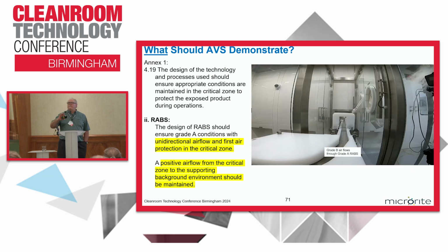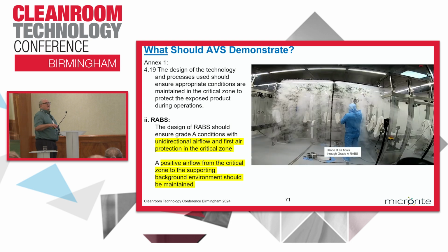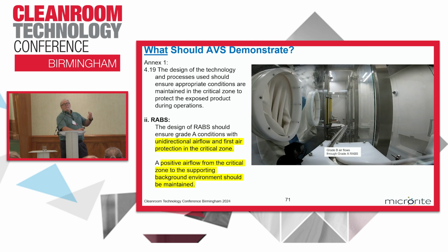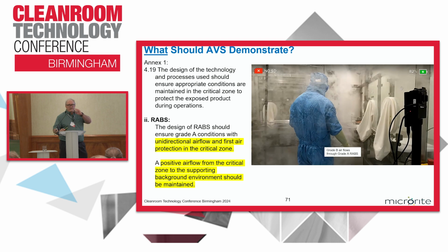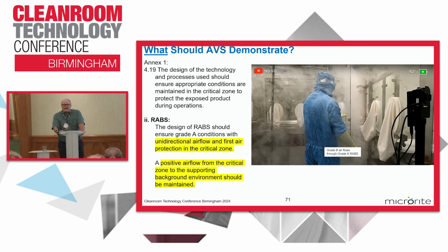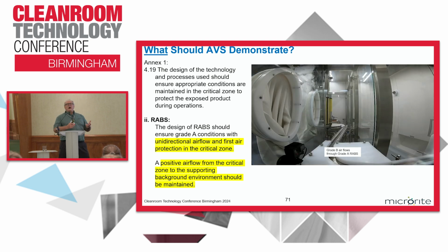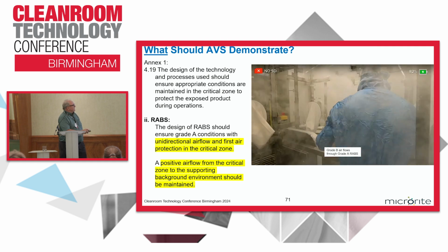The point being, this problem would have been avoided at the start of the project had they decided to really look at the design, do computational fluid dynamics, model it, and then you can address the issue. A lot of times, CFD is a wonderful tool. Can't stress it enough on new projects or even retrofitting projects that have problems, because it allows you to create a model, and with that model, that gives you a tool to make changes before you cut plastic, before you cut metal, before you do these things. And then you can use airflow visualization to help validate it.